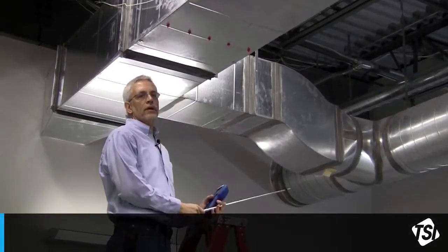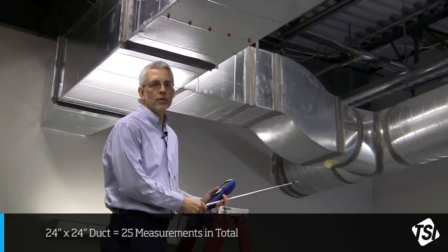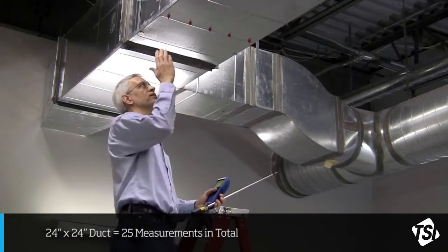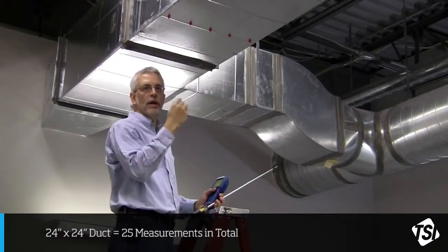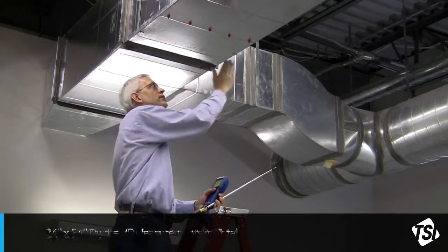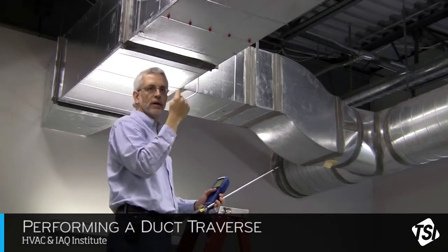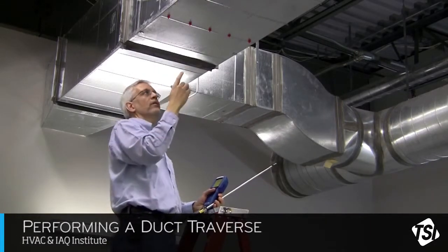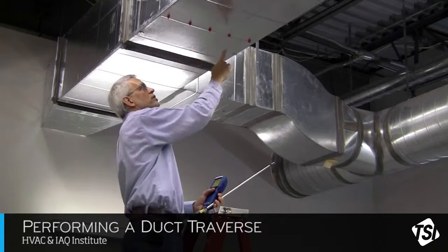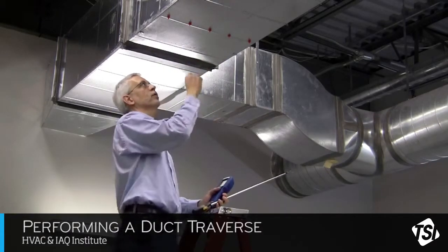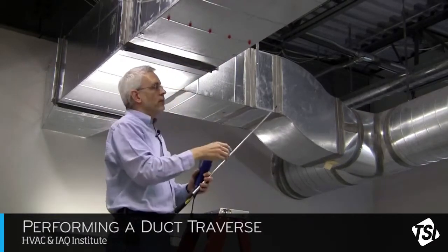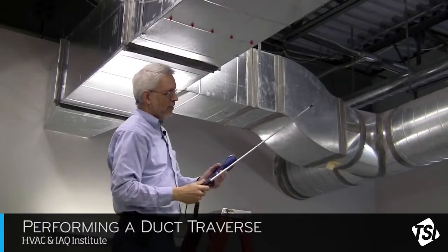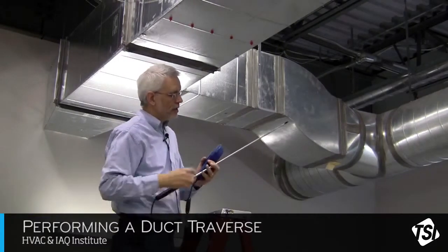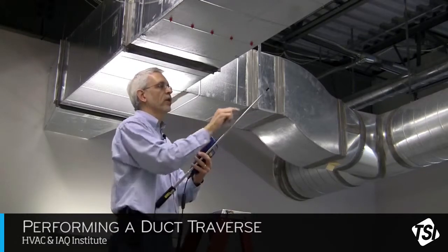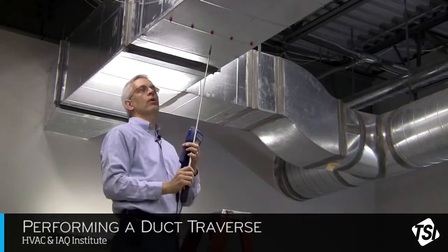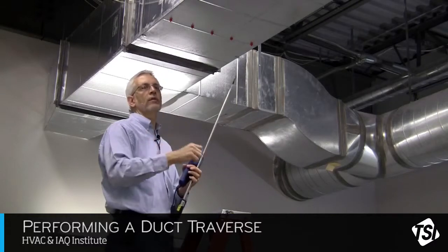For a rectangular duct, the log-T method prescribes on a duct of this size 5 measurements across the duct at 5 locations at each point within the duct. Before climbing the ladder or before doing my traverse, I would have, of course, drilled holes in my ductwork at the proper locations. My probe on the 9565 thermal anemometer is conveniently marked with inch marks, and I know which locations I'm going to be measuring. So I'm just going to proceed and take a duct traverse now.